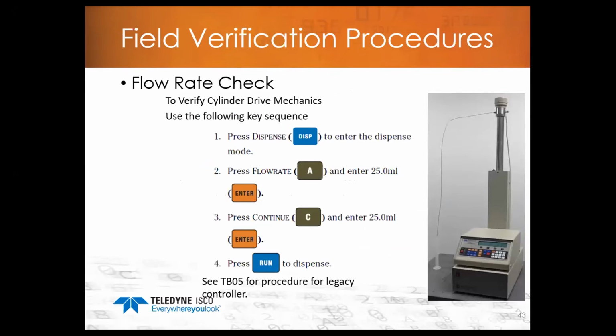On a flow rate check, the D-series pumps do not have a flow rate adjustment. The system uses a phase lock loop system. There is a tachometer or an encoder on the motor that provides constant feedback to the processor. With that feedback information, the processor is constantly able to monitor the flow rate and constantly adjust it based on that feedback from the tachometer and the flow rate that you've set.